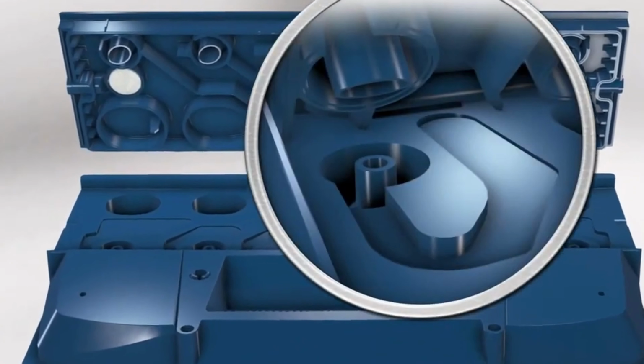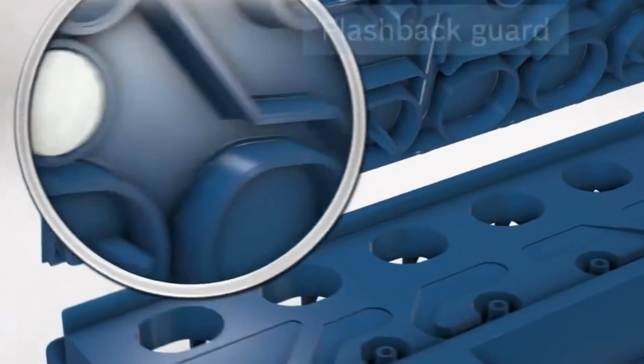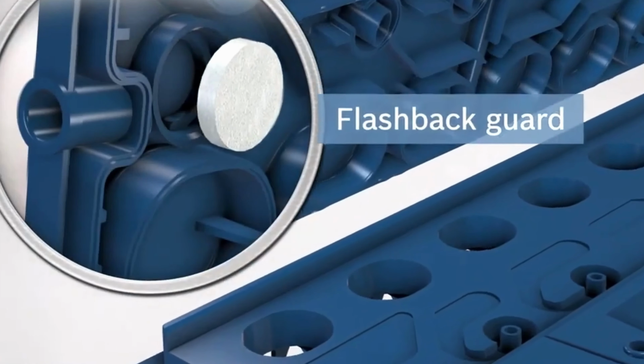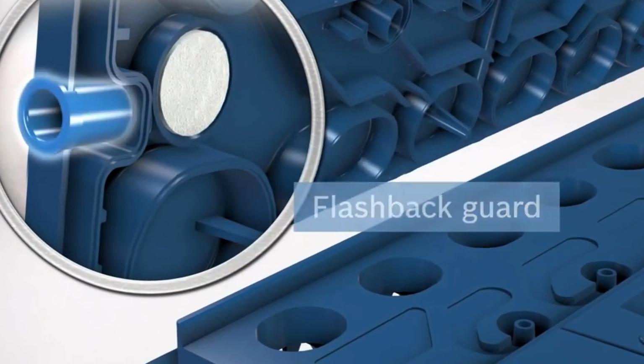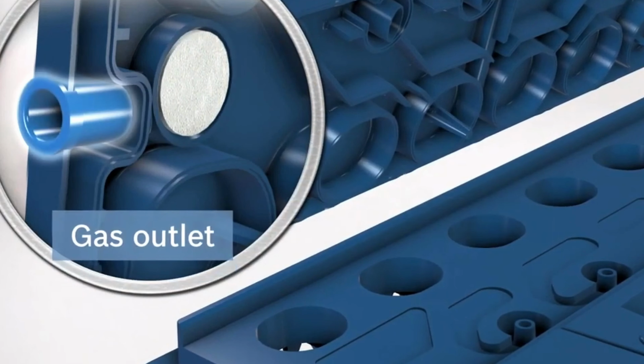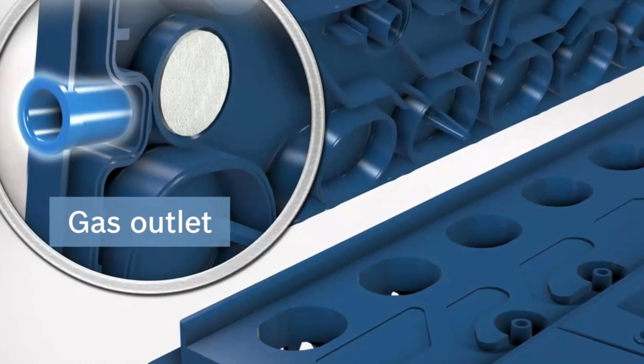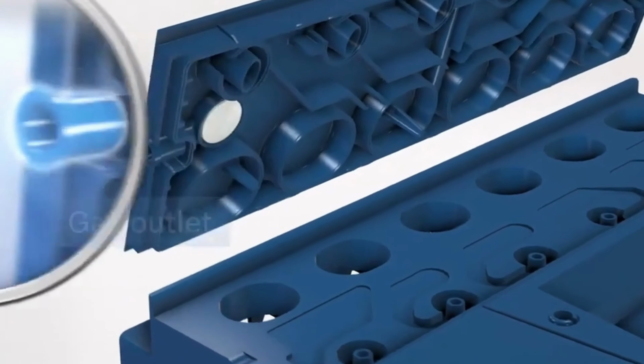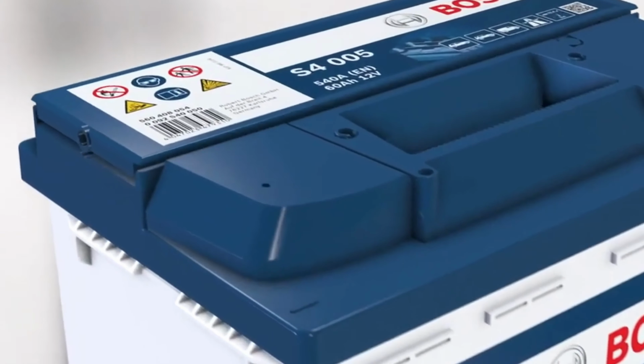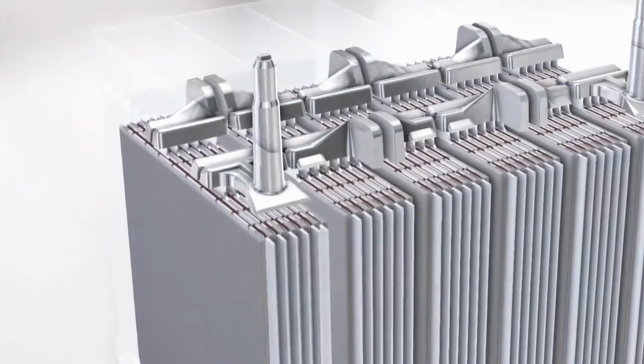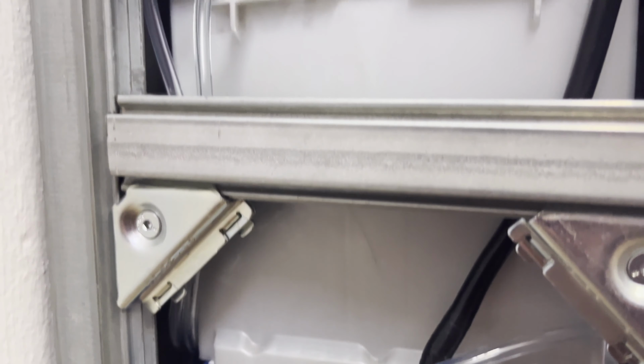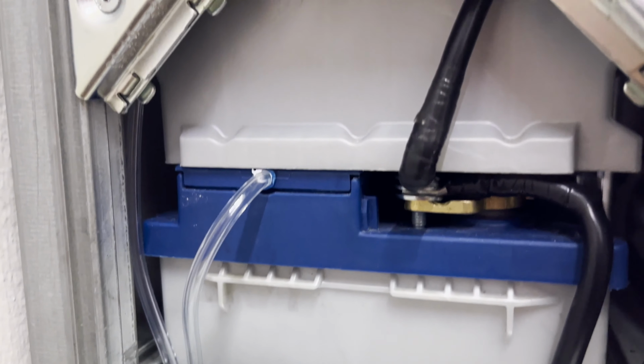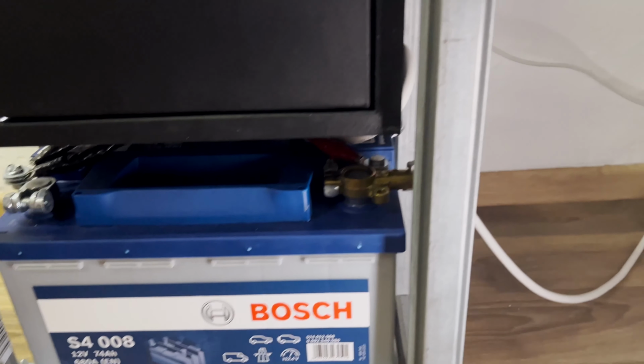You will say that these batteries have two emergency vents on the sides, through which vapors can still escape to the outside. And you will be right. If the recommendations for charging or operating these batteries are not followed, they can indeed emit hydrogen or vapors of sulfuric acid. Therefore, just in case, I connected tubes to these emergency outlets and led them into the entrance, which is in turn a well-ventilated area.